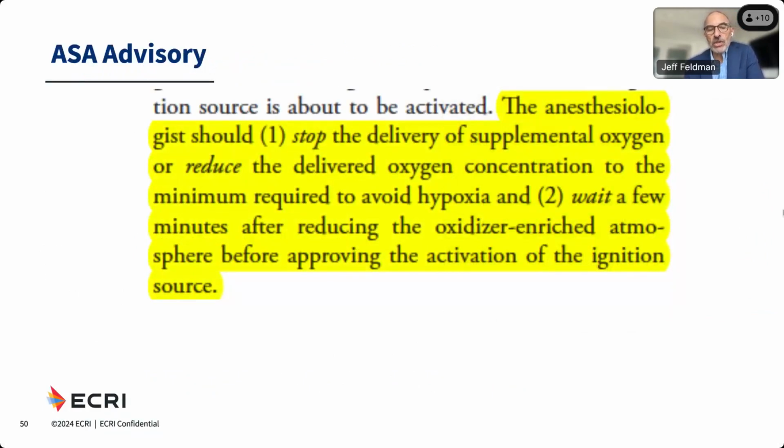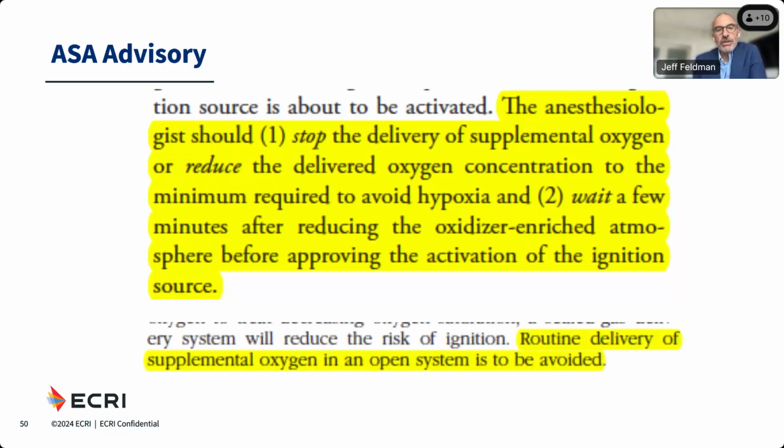There is some misleading information, even though there's been a lot of work by the American Society of Anesthesiologists, the APSF, the FDA, ECRI, many organizations to foster fire prevention. There is a little bit of misleading information that's still in the literature. And this relates to the ASA advisory, which was first published around 2008 or 9, I believe. But part of their prevention strategies recommends communicating with the surgeon, stopping the delivery of oxygen prior to igniting a heat source, and then waiting for the oxygen to dissipate from the environment. Next slide, please.